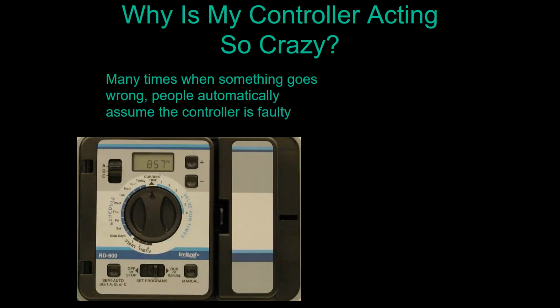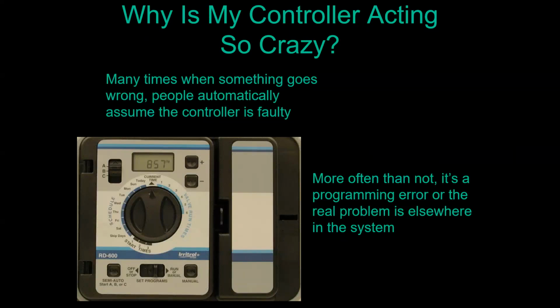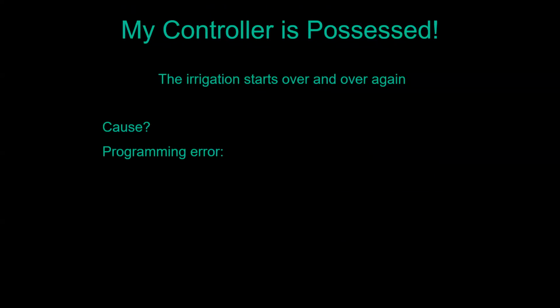Things weren't working properly, and they identified their entire irrigation system with that timer hanging on the wall, because that's the part they can see. So that's what they always assumed the problem was. Where in a lot of cases, it's actually often a programming error, or the real problem is somewhere else in the irrigation system. One of my favorite calls was from a sweet little old lady who was convinced her controller was under some sort of demonic possession, because her 3 sprinkler stations would run through and then start up and run through the 3 stations again, and then start up and run through the 3 stations again. So obviously she felt that was a malfunctioning timer, but this was really a programming error. She tried to outsmart her timer, and she lost. She put in extra start times. She thought those start times were individual start times for individual stations.